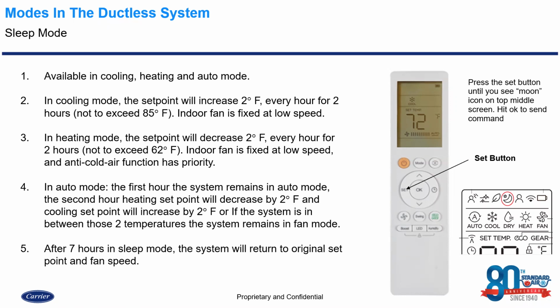Now, in the auto mode, both of these rules apply. So in cooling and in heating mode, we're not going to allow the set point to go above 85 degrees or go below 62 degrees. And depending on what we need, that set point will increase or decrease 2 degrees every hour for 2 hours, not to exceed those thresholds that I just mentioned.